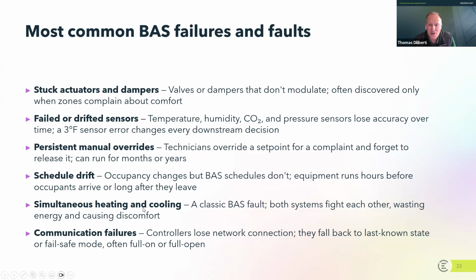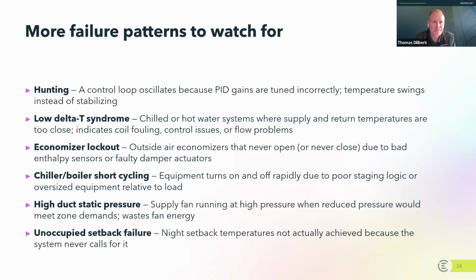I mentioned this earlier about heating and cooling with a deadband. So heating and cooling occurring at the same temperature. You want to make it so systems have temperatures where it's not heating or cooling. And communication failures too, that happens with everybody. So just make sure you're checking your buildings consistently and identifying those sooner rather than later. Other things to look for is if you're trying to find the right temperature in a space, sometimes it might be a little bit low or a little bit high. A term in the industry is called hunting. It's hunting for the right temperature.